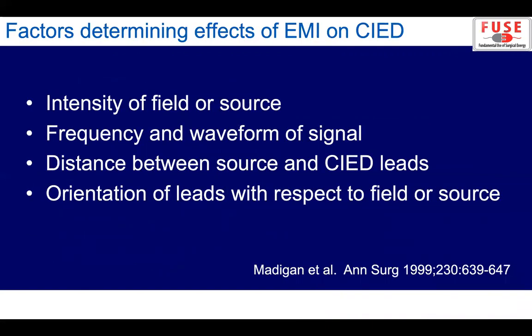What factors determine the effects of EMI on a CIED? Basically, this comes down to the intensity of the field or source, the frequency and waveform of the signal, the distance between the source and the CIED leads, and the orientation of leads with respect to the field or source. Essentially, in other words, what device are you using, what mode, what energy level, where did you put the dispersion pad, and what's the current path from the device to the dispersion pad.